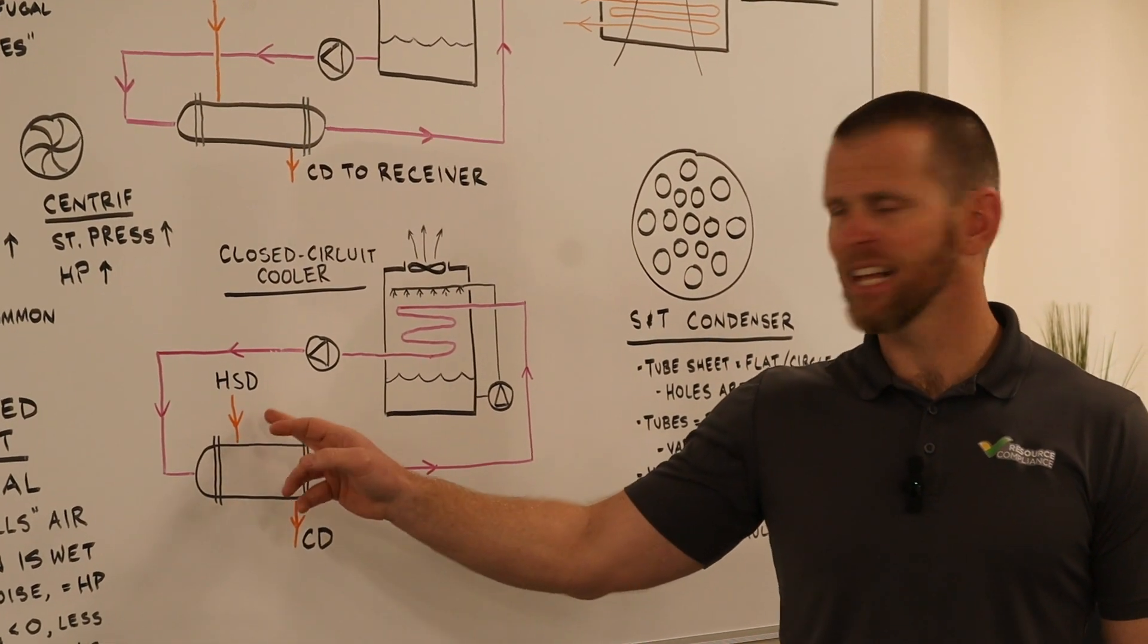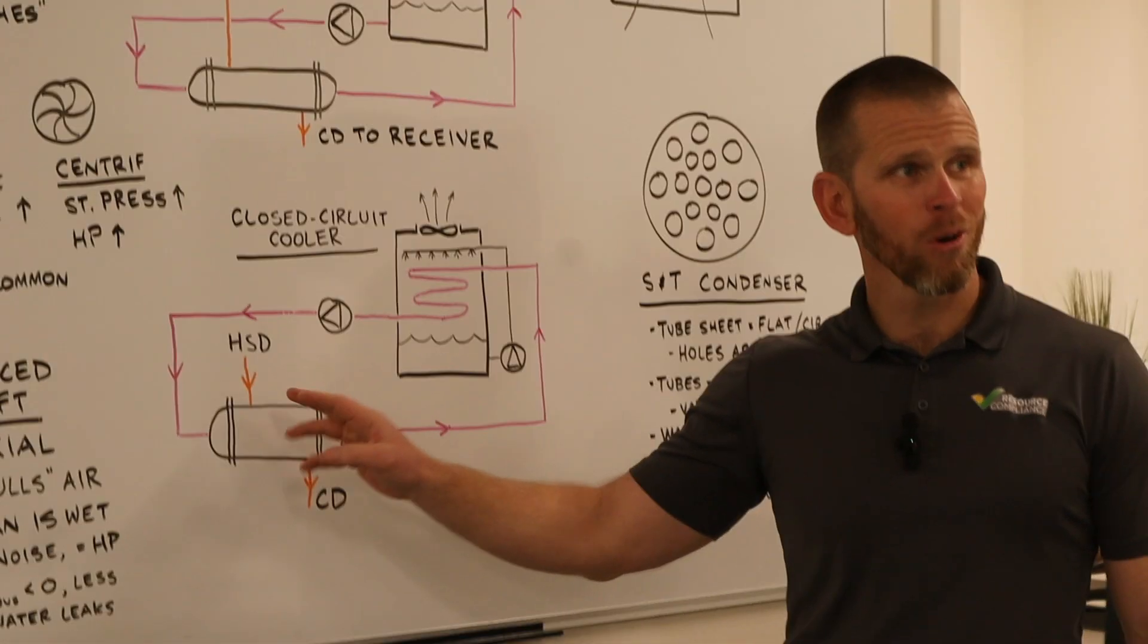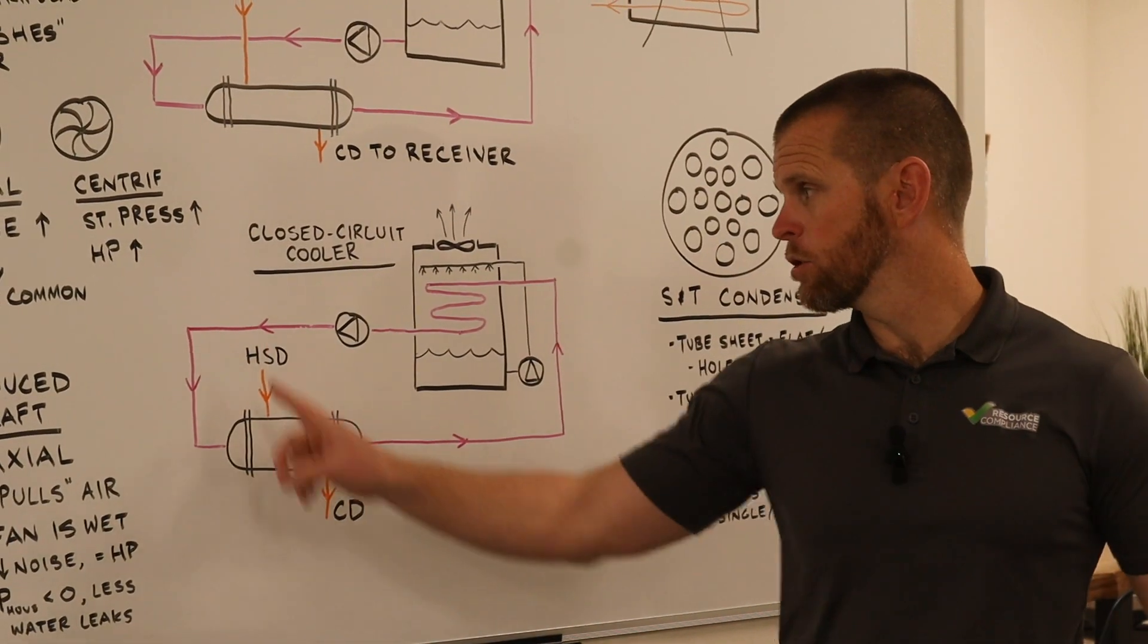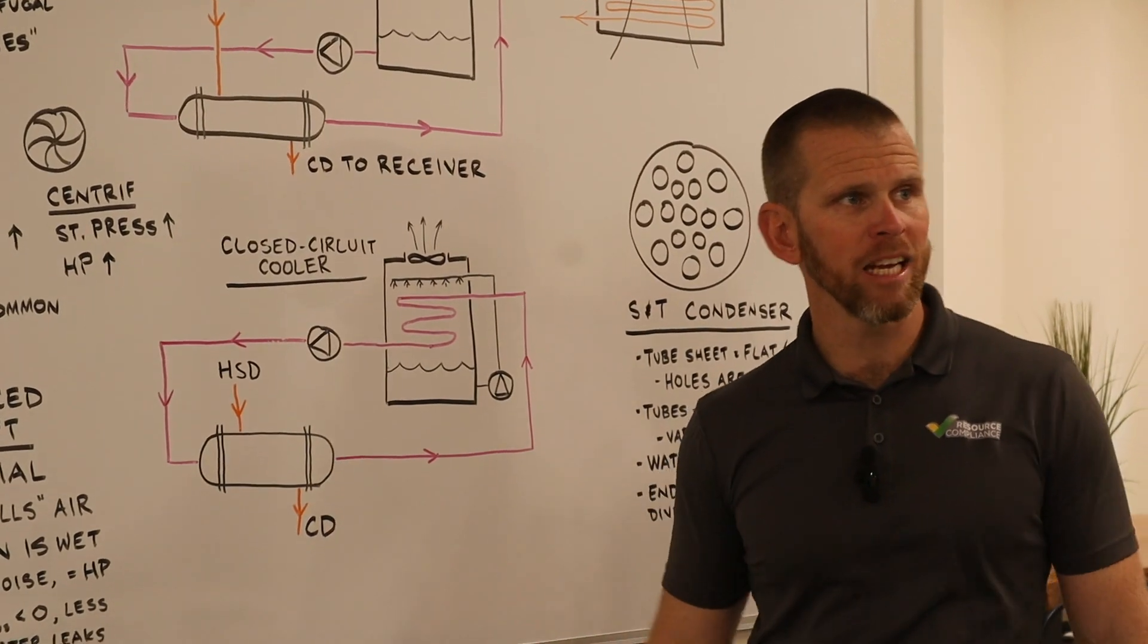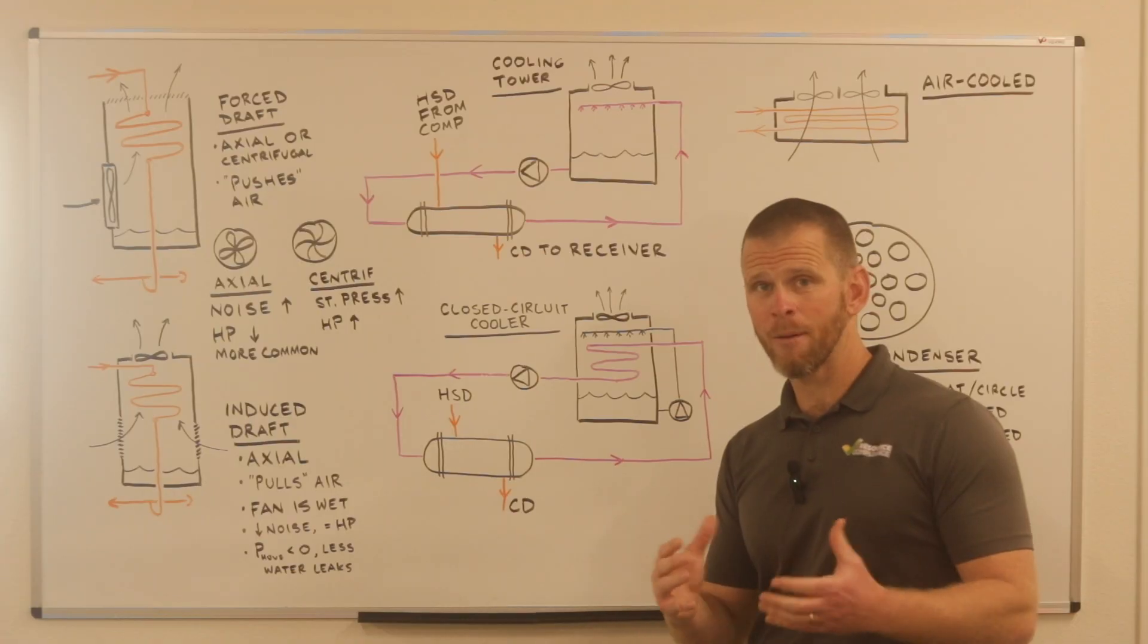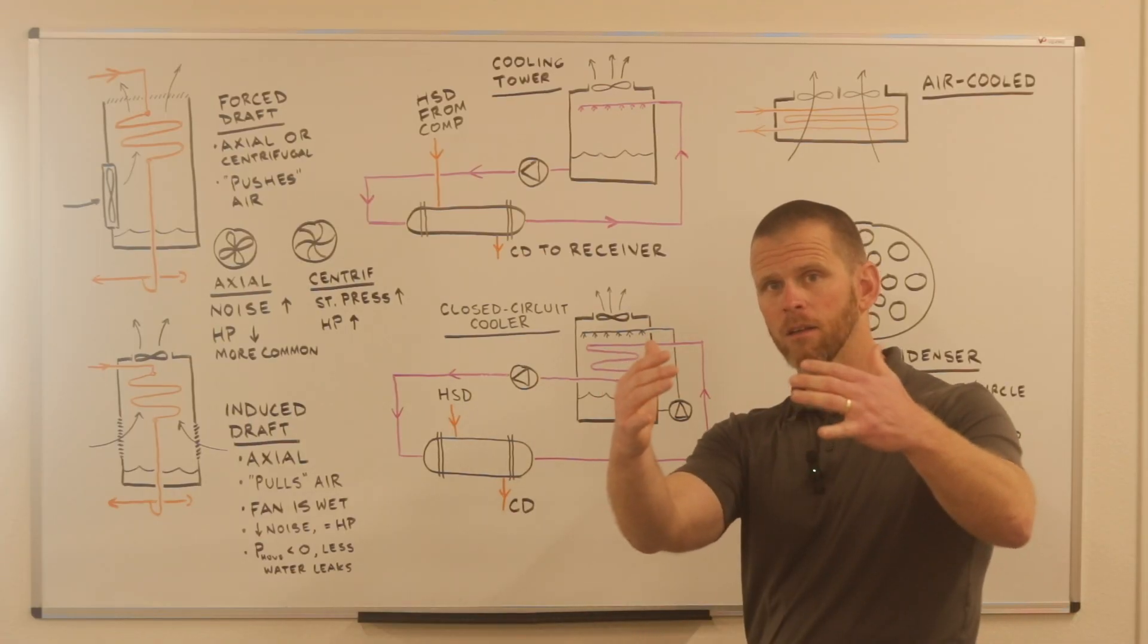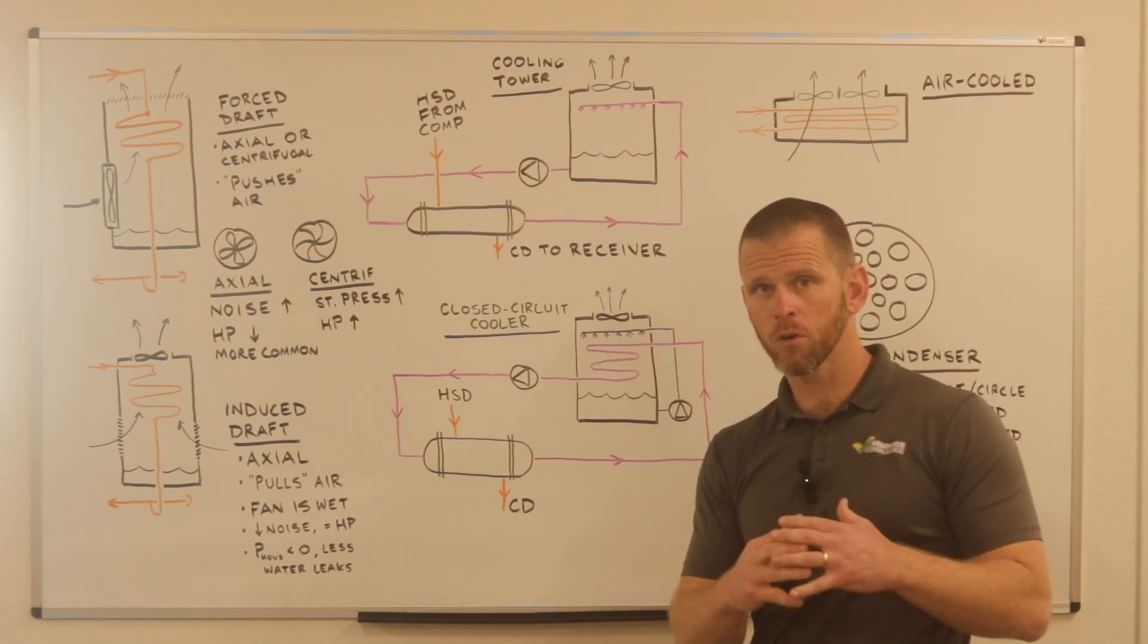The heat that's in the superheated vapor is getting rejected into the water that's being circulated through this shell and tube heat exchanger. In the process of doing that, the refrigerant is de-superheated first.